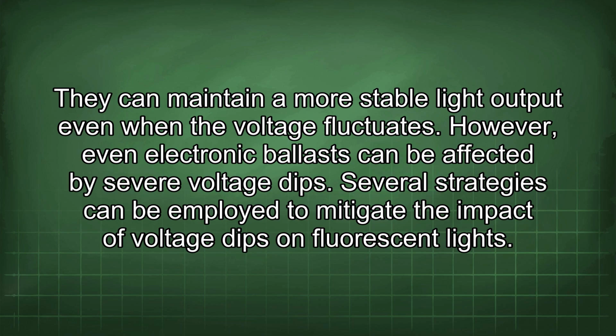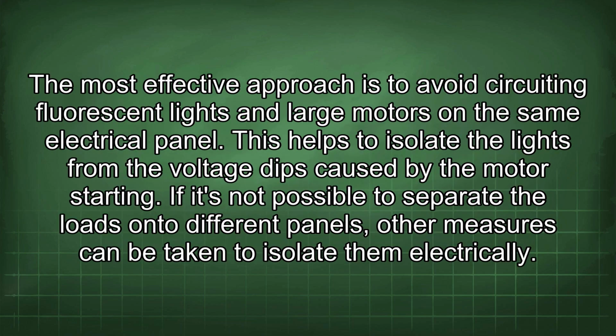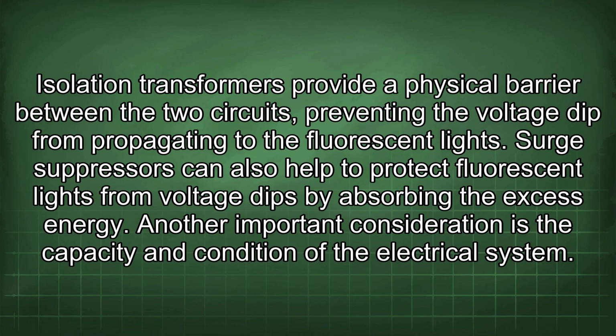Several strategies can be employed to mitigate the impact of voltage dips on fluorescent lights. The most effective approach is to avoid circuiting fluorescent lights and large motors on the same electrical panel. This helps to isolate the lights from the voltage dips caused by the motor starting. If it's not possible to separate the loads onto different panels, other measures can be taken to isolate them electrically. Isolation transformers provide a physical barrier between the two circuits, preventing the voltage dip from propagating to the fluorescent lights. Surge suppressors can also help to protect fluorescent lights from voltage dips by absorbing the excess energy.